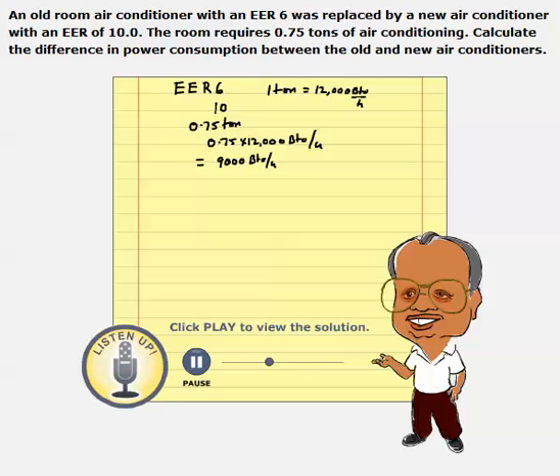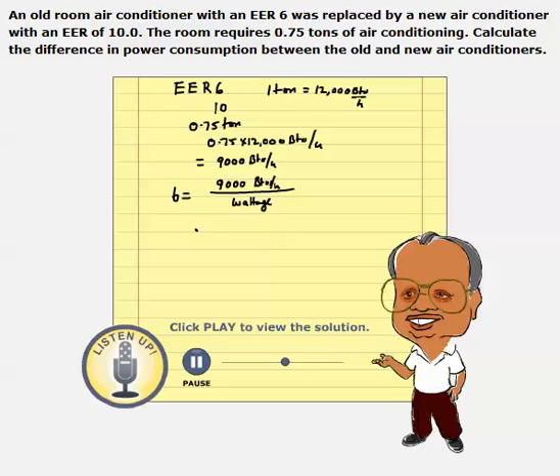So to pull out 9,000 BTUs per hour with an air conditioner of EER equal to 6, we are pulling out 9,000 BTUs per hour. The wattage is equal to 9,000 divided by 6. That happens to be 1,500 watts.